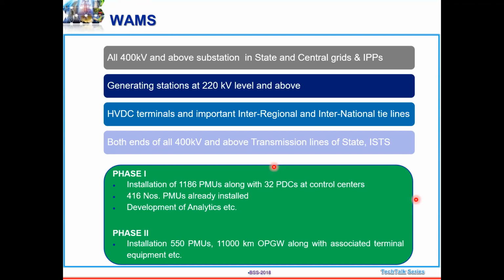Earlier, we used to plan for satellite communications, but because of the time lag delays and all, we are going for OPGW communication now. And KSEB is also introducing OPGW throughout its transmission system up to 33 kV. As you all know, it is KFON, a KSITL-KSEB joint venture. We are planning to have OPGW in all 400 kV, 220 kV, and 110 kV transmission systems, including 66 kV. And down the line, we will have ADSS, all-dielectric self-supporting cables, in 33 kV systems also.